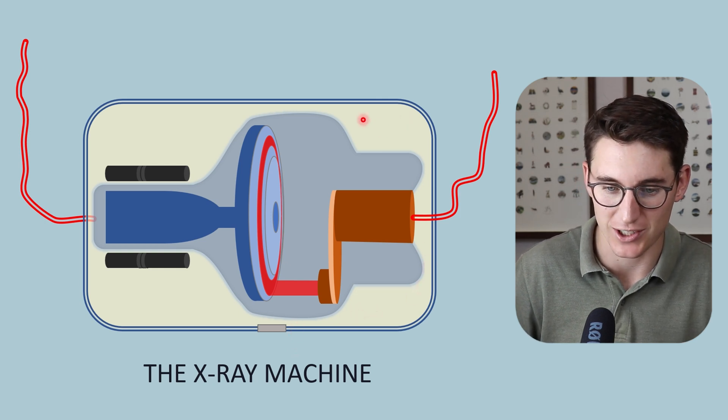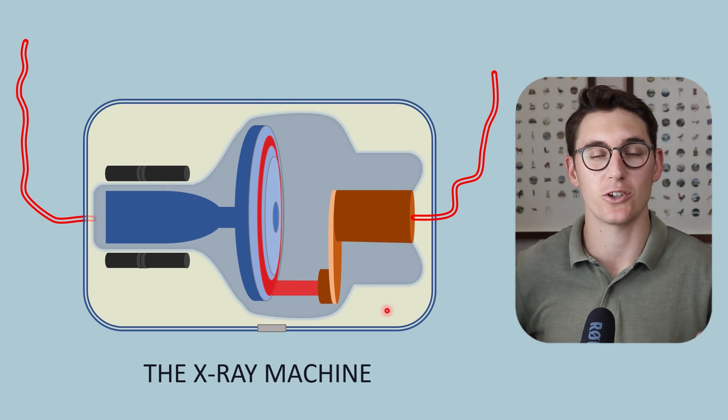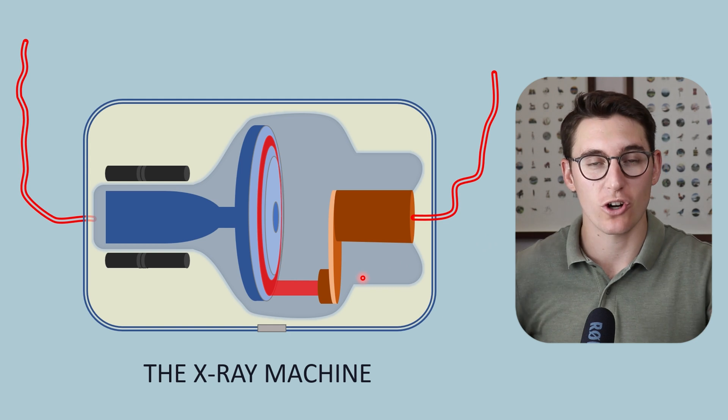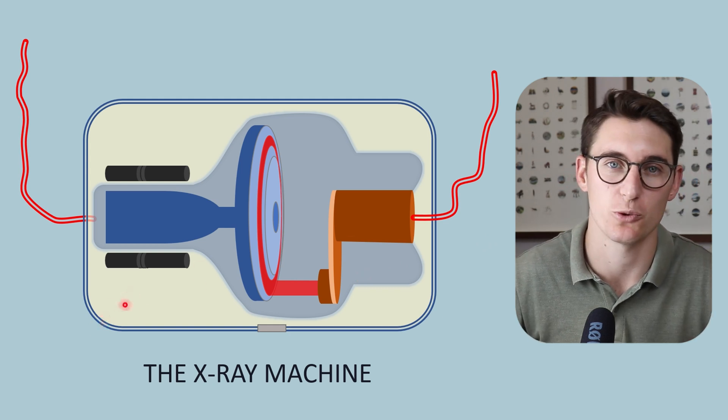Then we can see that there is this insulating oil that surrounds this glass envelope. The insulating oil moves around within the x-ray tube, transferring heat away from our anode and towards our tube housing.